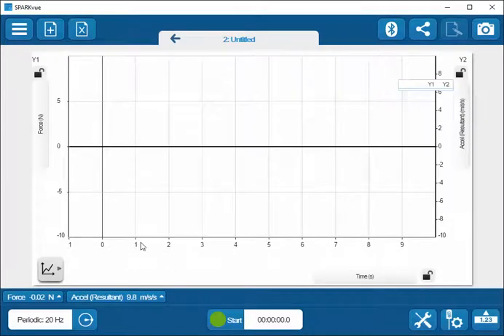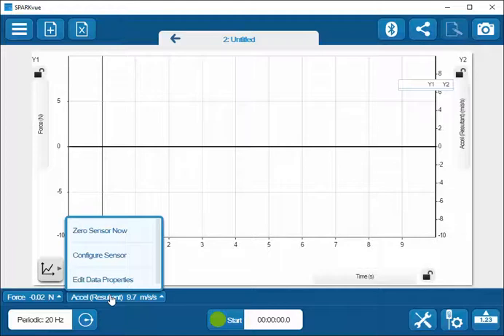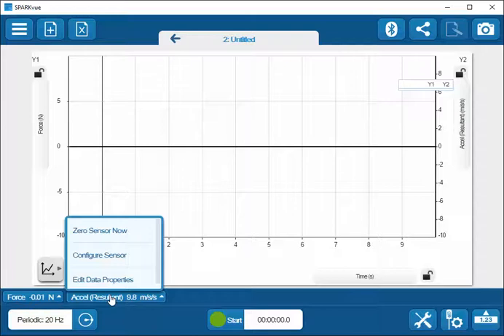Depending on the type of sensor that I'm accessing, I can click on this acceleration menu, and you can see that some of the options are not available for this sensor because it is not directly able to be calibrated.